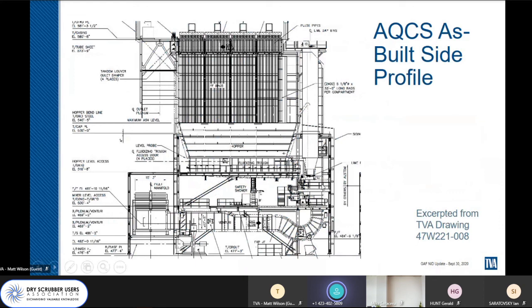So this J-duct is the J-duct reactor, where the majority of the SO2 removal takes place. According to Alstom, 80% plus of their SO2 removal takes place in the J-duct reactor. Alstom says approximately 20% takes place across the bags. Just queuing in on some of the questions from last time. Has TVA validated that? We have not. We have not gone right here and tested SO2 removal across our J-duct reactor and across the bag house proper.